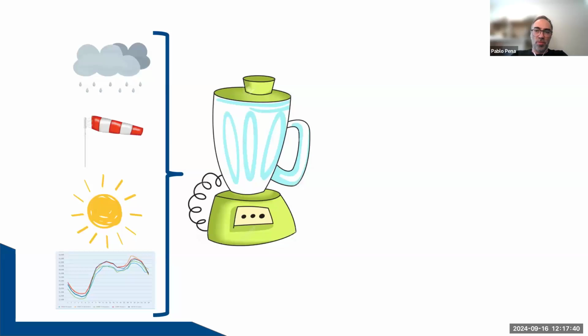We move from a deterministic methodology, which focuses on worst-case scenarios, to a probabilistic approach using the Monte Carlo method, sequential Monte Carlo. This new approach allows us to analyze the diversity of load flow patterns. By using repeat random sampling, we simulate the optimal dispatch for the future study year, taking into account rainfall, wind, irradiance, and demand curves, hour by hour.